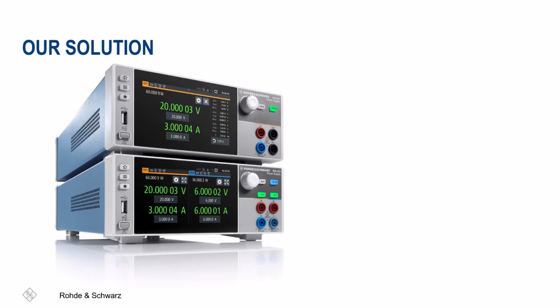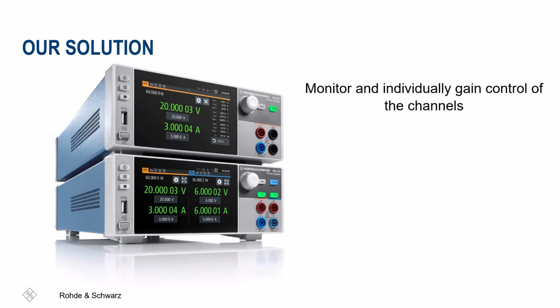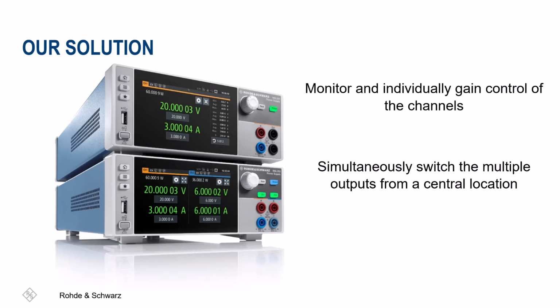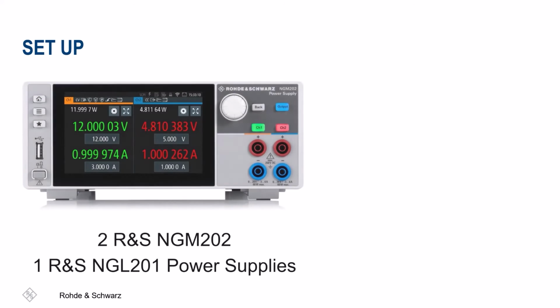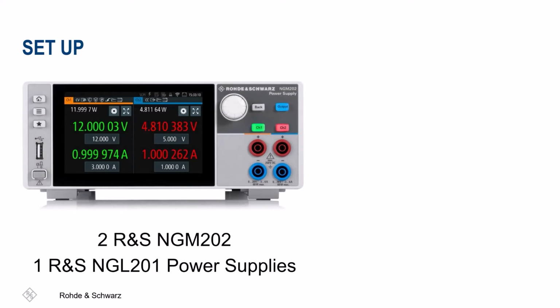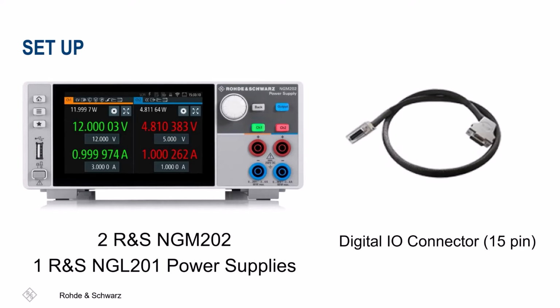Rohde and Schwarz provides a great solution that gives you the ability to monitor and individually gain control of the channels and simultaneously switch the multiple outputs from a central location. In this video, we will demonstrate how to remotely switch multiple outputs using two R&S NGM202, one NGL201 power supply, and a digital 15-pin input-output connector.